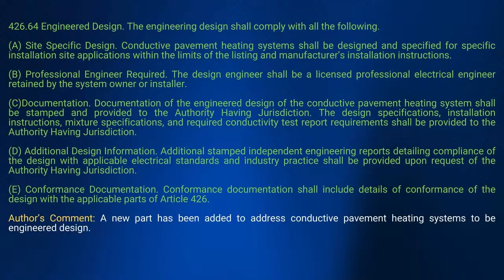One interesting thing is it gets into the design specifications—installation instructions, even mixture specifications—they're required to have a conductivity test report requirements provided to the authority having jurisdiction. So it's one thing to put this type of system in, but you've also got to show your mixture specifications and how it's installed, and have it documented.